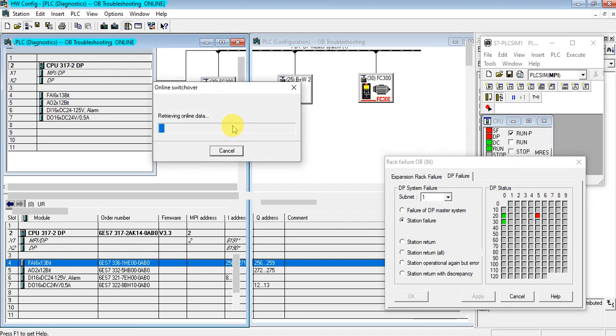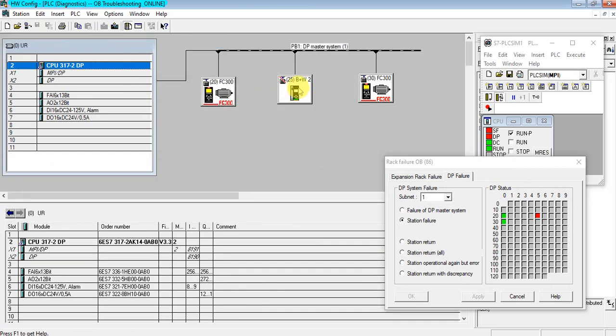It's showing system fault in the DP fault. See, slave 25 is missing. Let's see the diagnosis buffer.